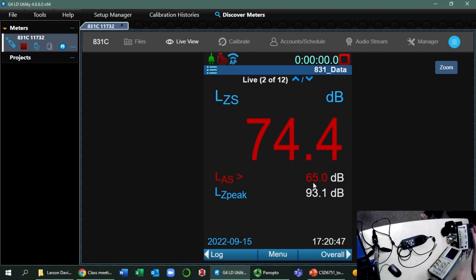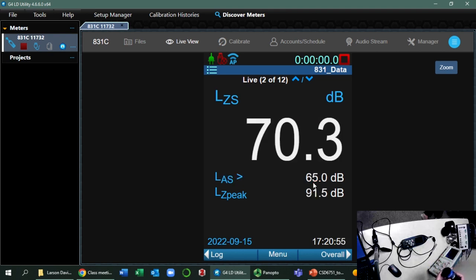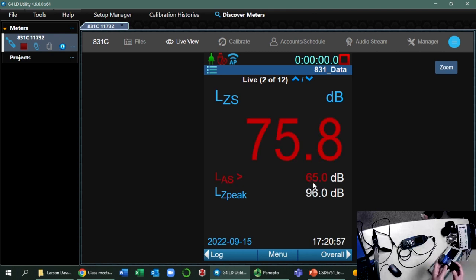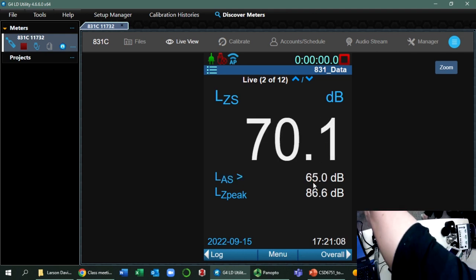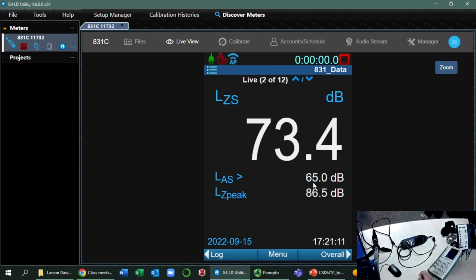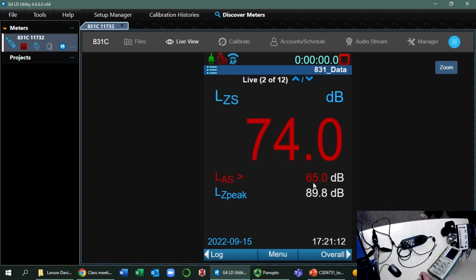So then comes what they call the acoustic calibrator. This one is slightly different from the one shown on the slide, but very similar—this one produces exactly 250 hertz at 114.0 dB SPL. Let me press the button, and you folks pass it along and listen—yeah, that's 250 hertz.